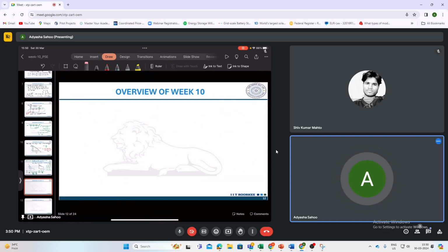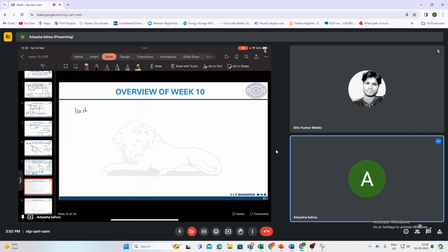And after that, governor modeling. So first we saw the isochronous governor. To that, we added the feedback, that is your droop R, for two or more generators, and then after that, we saw that we can also add the load reference set point.